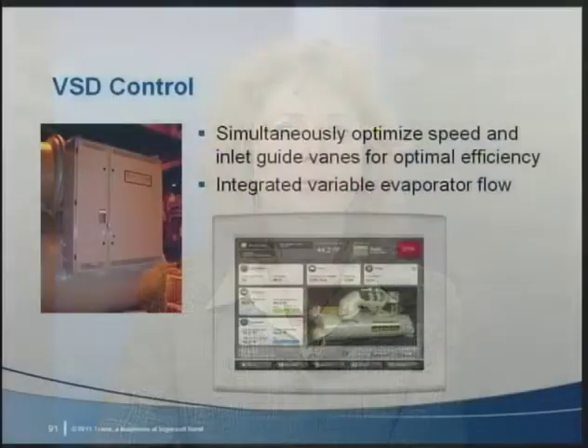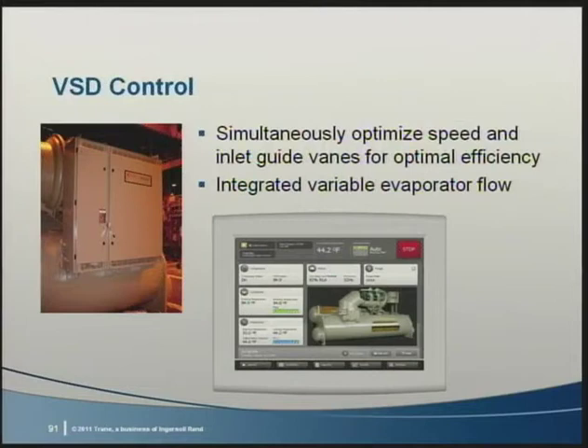As you can see, having a controller that is capable of reacting to rapid changes in flow will provide efficient operation and significantly better temperature control in your system. Another control upgrade benefit is the coordination of work between the inlet guide vane and the variable speed drive. Simultaneous optimization of speed and capacity control is important when trying to get the chiller's sweet spot quickly in order to save energy. This feature of the latest generation of controls is particularly important when flow is changing at the same time. Having a controller that is retuned for the present flow rate makes variable flow and variable impeller speed possible at the same time.